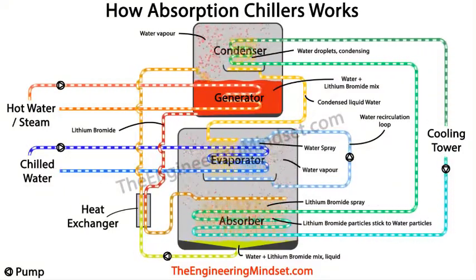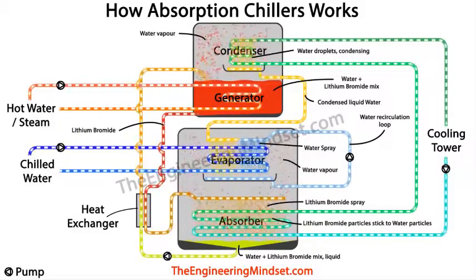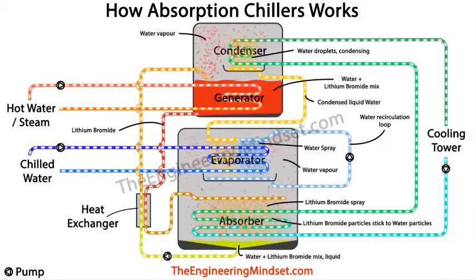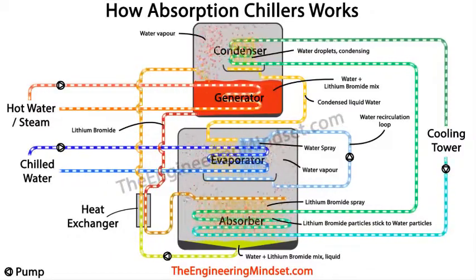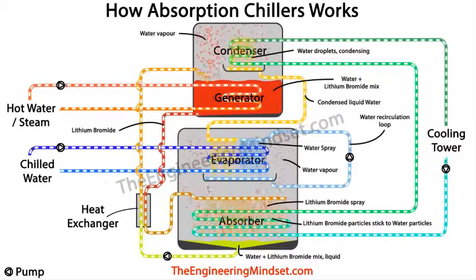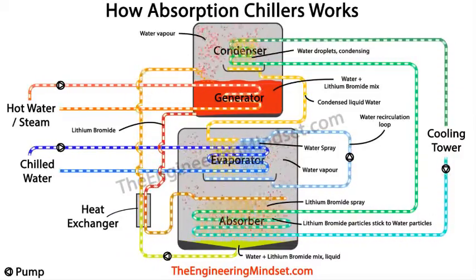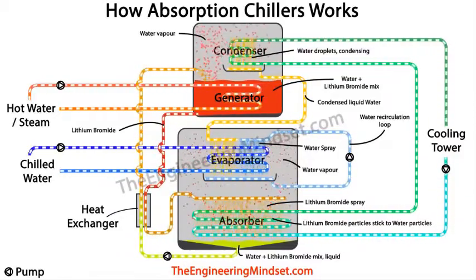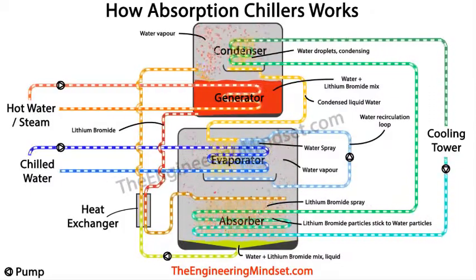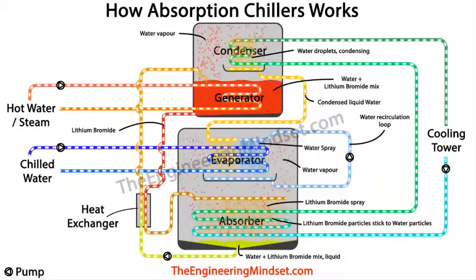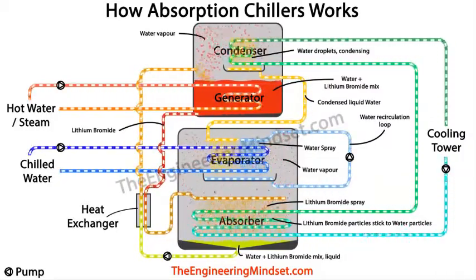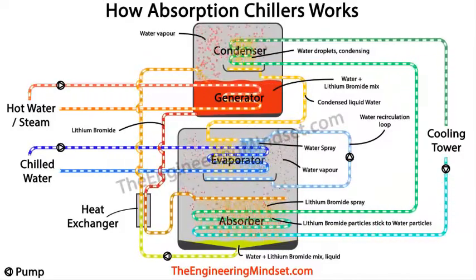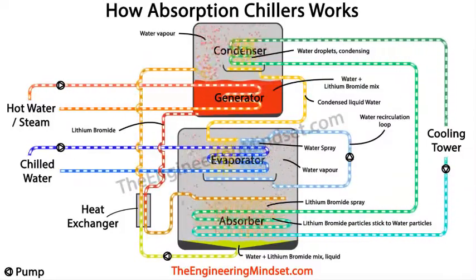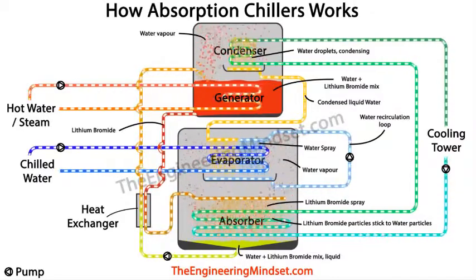Now all of this water that's evaporating into water vapor and steam will build up and collect around the evaporator chamber, and this water vapor or steam is then attracted and pulled towards the strong lithium bromide solution being sprayed in the absorber, almost like a magnetic force. The attraction is so strong that water particles flow by themselves straight to the absorber to be together with the lithium bromide particles. This strong, almost magnetic attraction between the water particles and the lithium bromide particles is what causes the vacuum in the chamber.